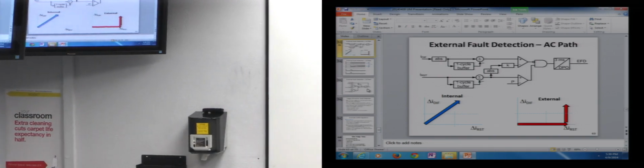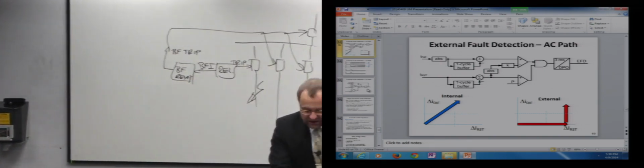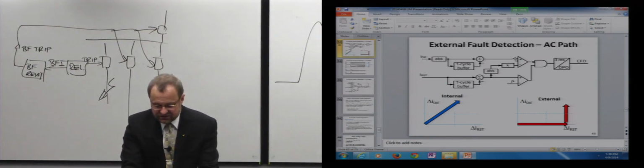So my logic works like this. I look at the increase in the differential signal, and I subtract the value that is 1 cycle old. If I don't see an increase in the differential signal and I see an increase in the restraining signal for 3 milliseconds, I declare an external fault. So this logic basically says that an increase in the restraining signal and no increase in the differential signal is an external fault. When I have an internal fault, both of them go up at the same time. So this signal is logic 1.